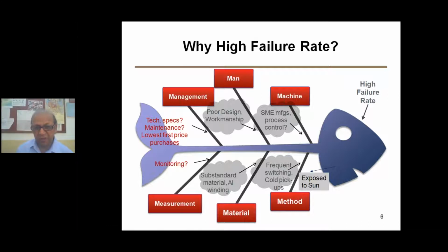Two things. One is switching: always when we switch on a transformer, some damage takes place. Another problem is the cold pickup problem. Cold pickup problem means when the power supply is gone, whatsoever may be the reason, for half an hour or 1 hour, 2 hours, and when you switch on after that, all the thermally controlled loads will be switched on. When they are all switched on, there will be a lot of load on the transformer, which may cause the failure. There will also be inrush current that may also damage something in the DTs.